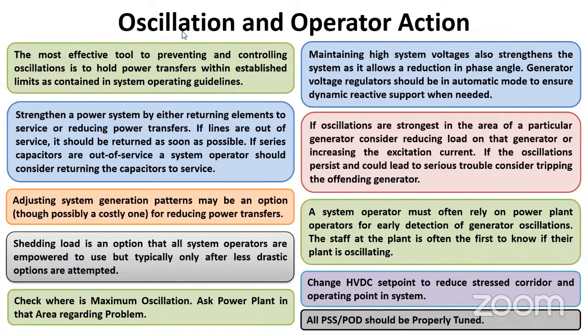This forced oscillation detection is a very challenging task for the operator, figuring out who is injecting the problem. So at that point, we collect information from all the plants to check whether any controller is having an issue. This is practical experience - most of the time we've tracked down that either the governor is malfunctioning, the valve is malfunctioning, or similar issues.